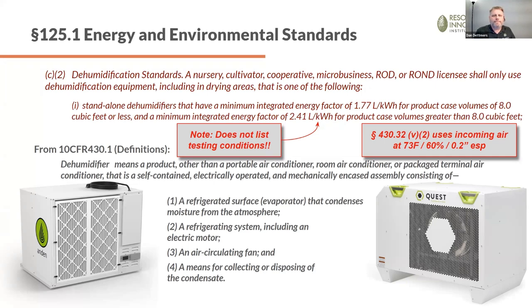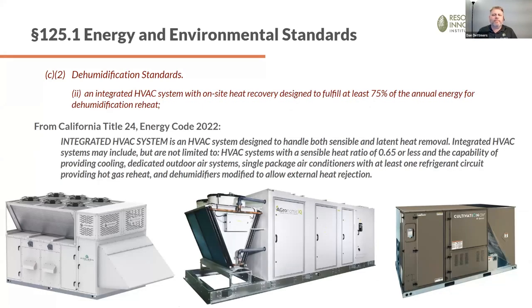The next piece of equipment to talk about is one that California kind of invented this term for as a catch-all integrated HVAC system. Looking across the bottom, the first unit on the left is a DOAS system, dedicated outdoor air system. These are used in the HVAC industry for spaces like supermarkets, swimming pools, and other spaces where you need to bring a lot of ventilation air in, but you need to do a lot of dehumidification of that air.